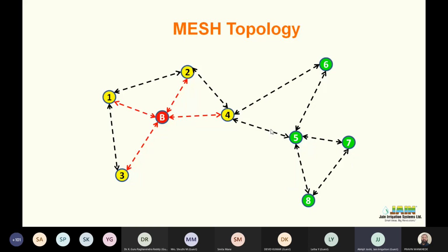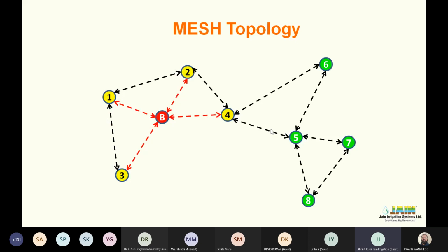So mesh topology has its own advantages and limitations. With mesh topology, you can go for continuous communication, and you can assure that the signal is being received by the RTUs. But mesh topology is battery hungry, a power hungry thing, because you want each and every RTU to repeat the signal continuously, meaning each RTU needs to be in wake-up mode all the time. So the power requirement for mesh topology is very high, which is why we have gone for solar power supply for these RTUs.